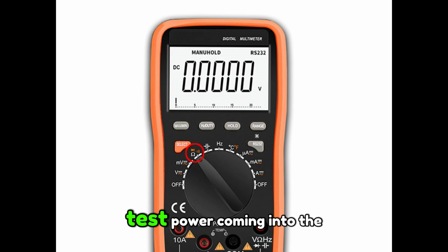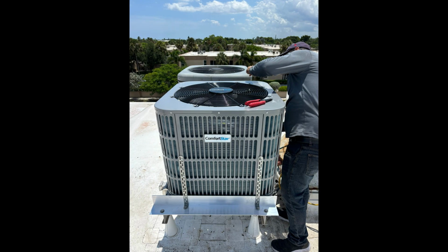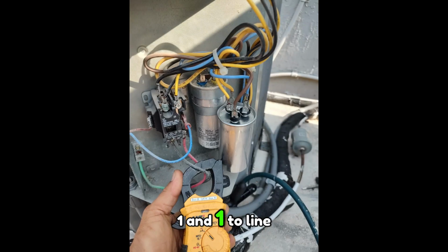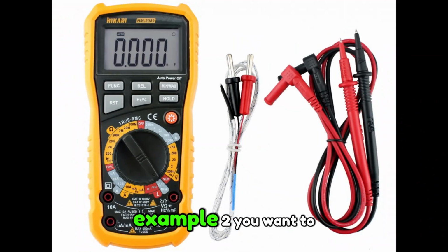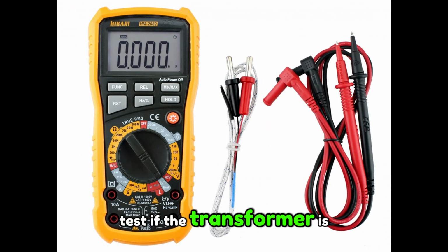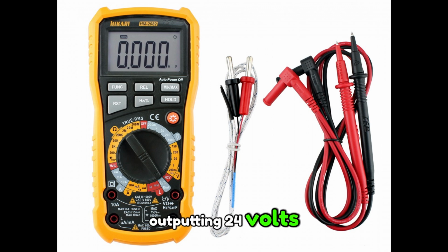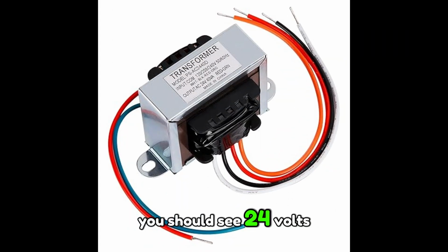Example 1, you want to test power coming into the air handler. Set your meter to AC volts. Touch one probe to line 1 and one to line 2. You should see around 240 volts. If not, the unit is not receiving power. Example 2, you want to test if the transformer is outputting 24 volts. Probe the two low-voltage wires coming out of the transformer. You should see 24 volts AC. If not, the transformer may be dead.